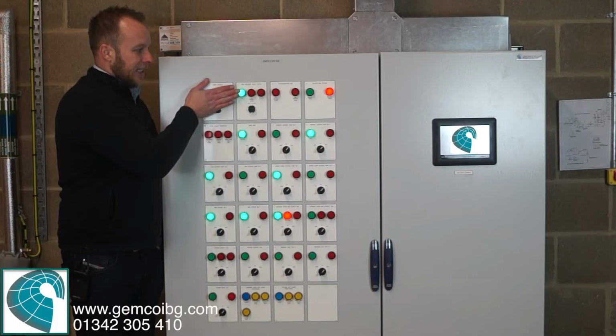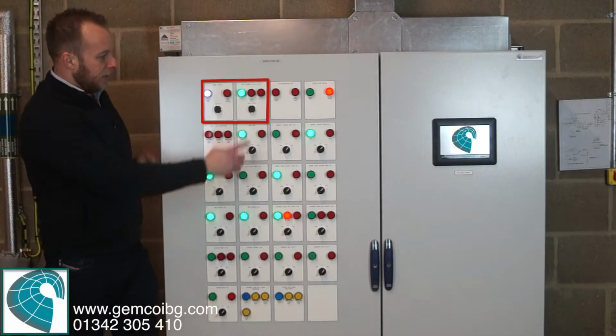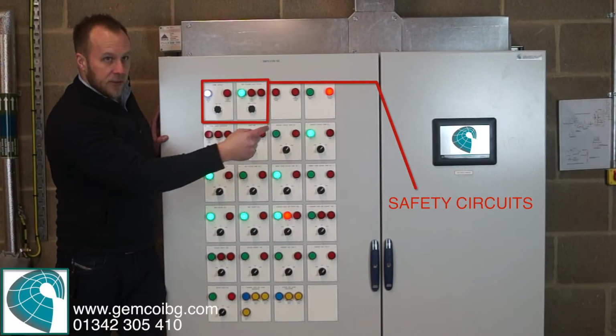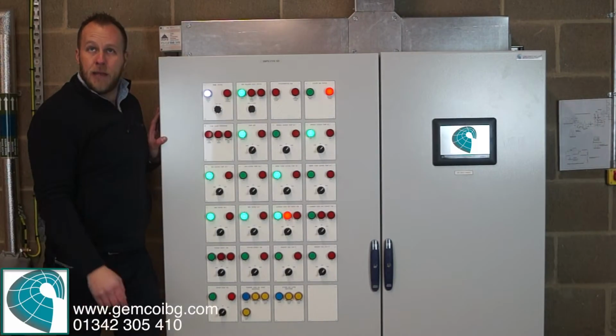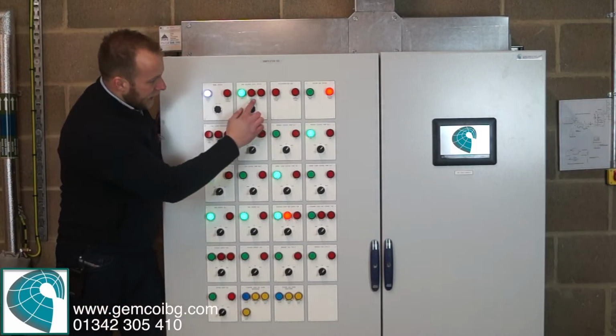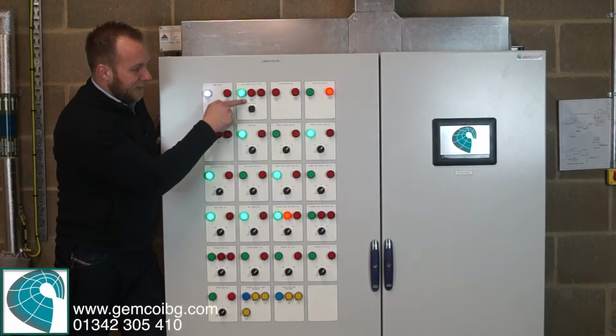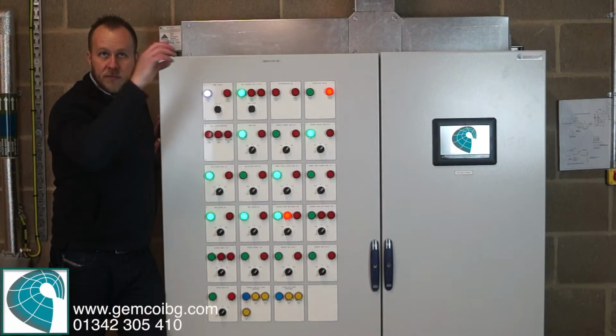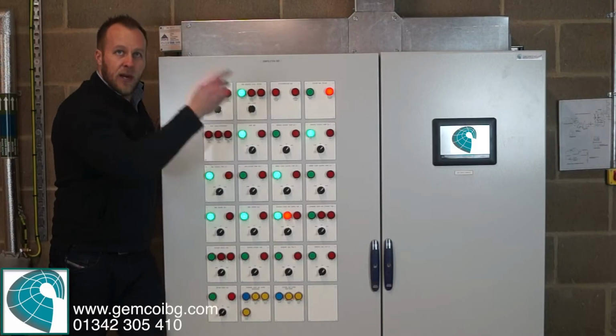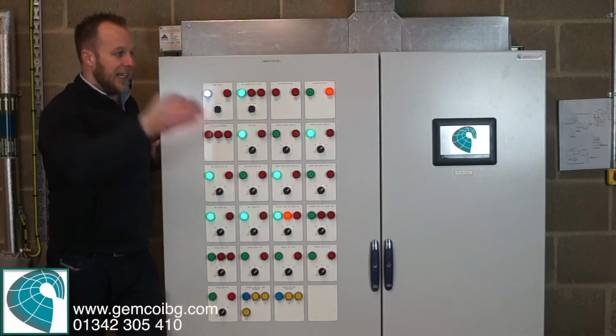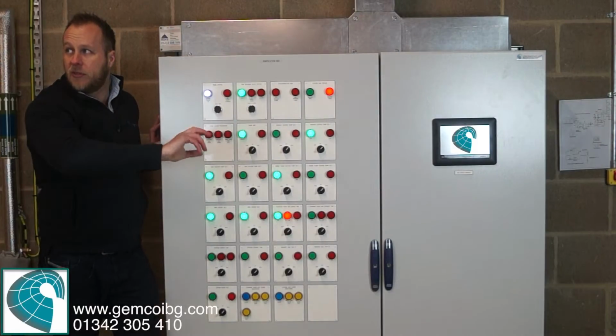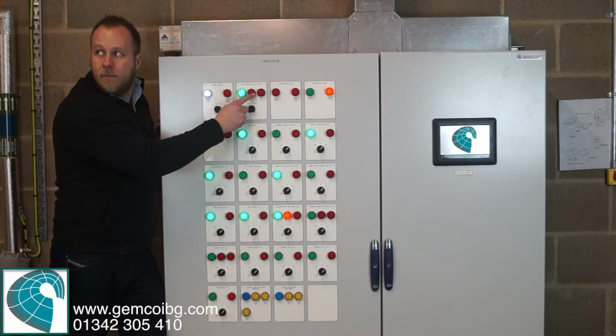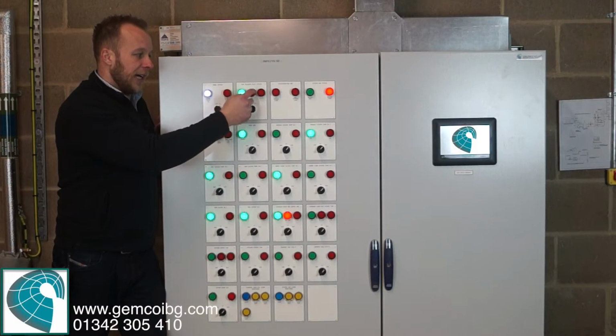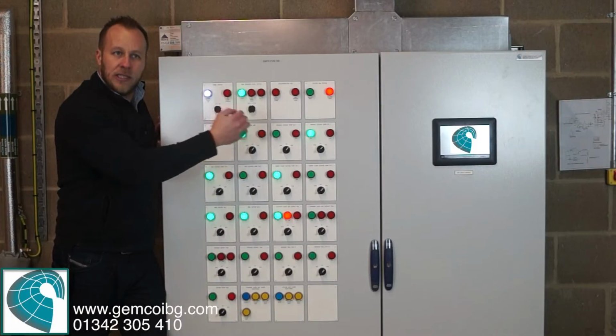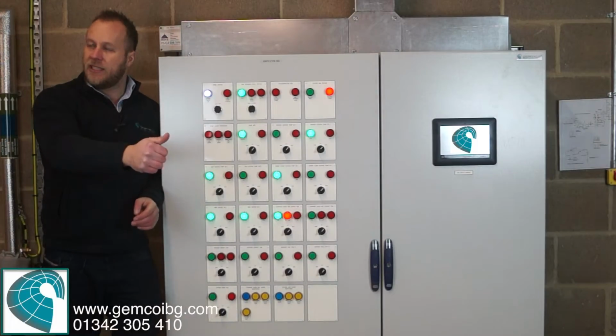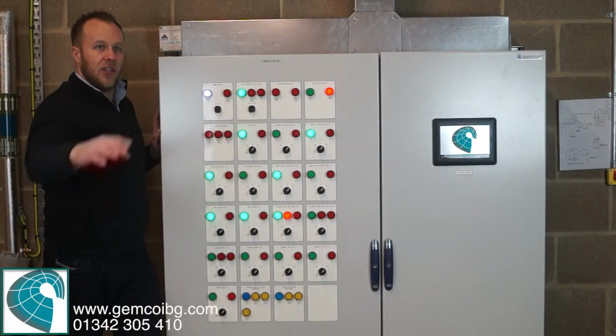If any of these red lights are lit, you're not going to have any plant. Now the way this works is, if you were to rupture the circuit by hitting the knockoff button or those links melt, the gas solenoid will shut and it will say closed, but it'll also tell you that the gas safety circuit has failed. Okay, because something's wrong. As soon as you rectify that problem, so say you put the fire out, you've replaced the link, or you've reset the knockoff button, and you reset that just by twisting it, this light will go out, but this light will stay on to let you know that you've rectified the fault, but the gas valve's still closed. It needs you to say, I'm happy, I want to reset the solenoid. And once that's the case, you press that button and the solenoid will open.